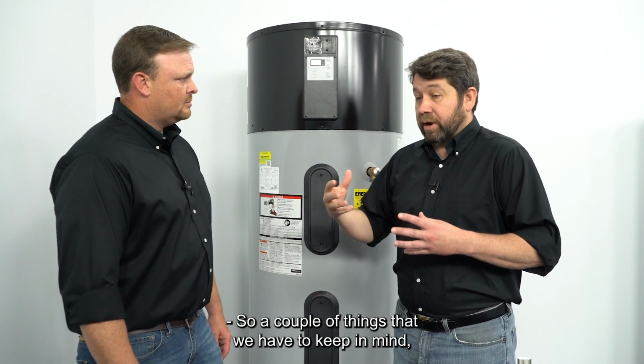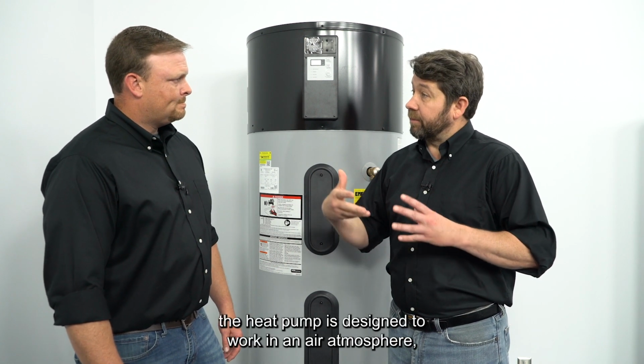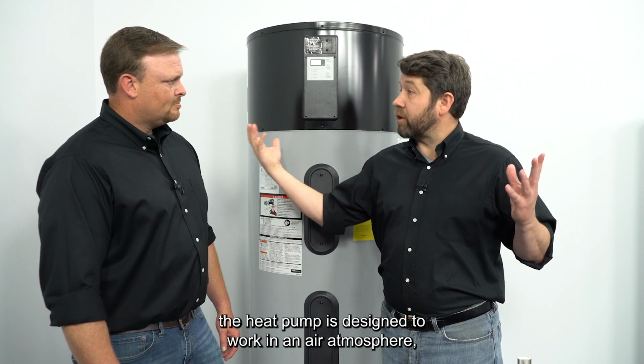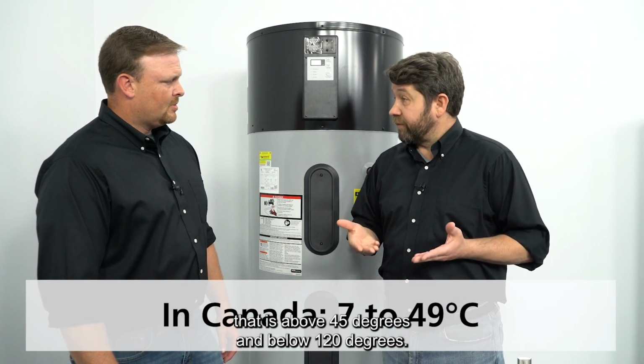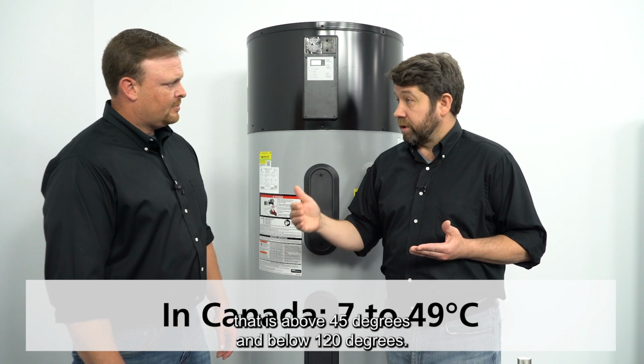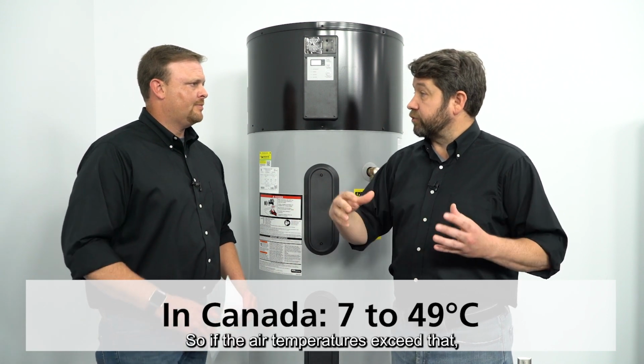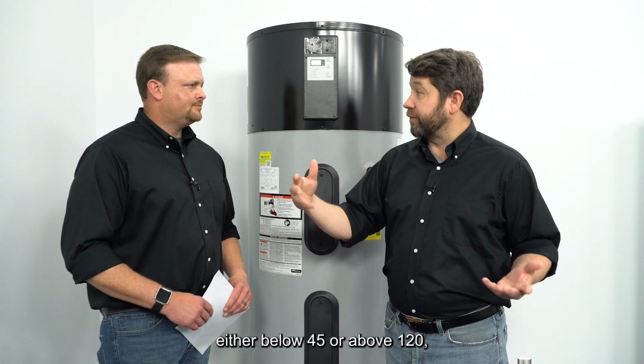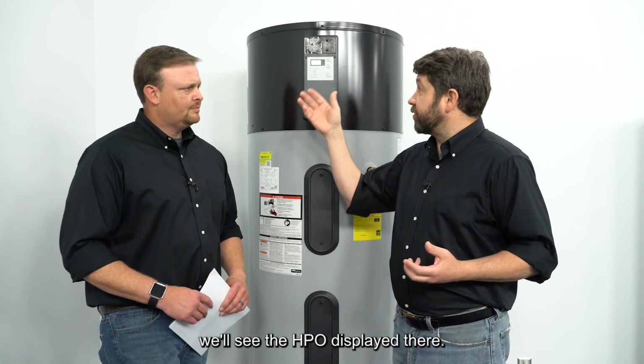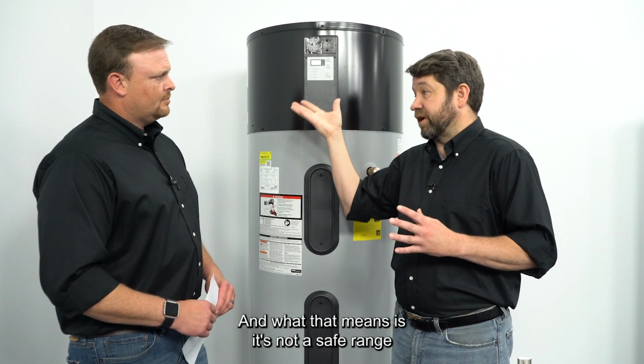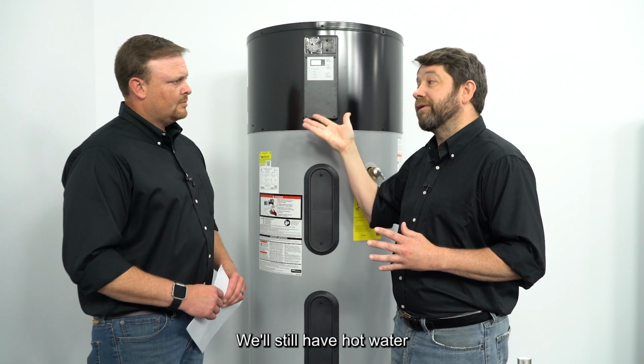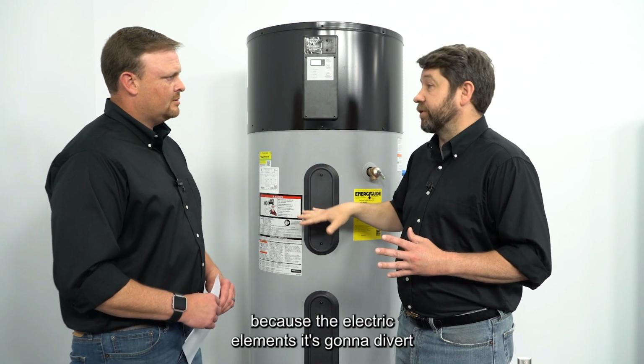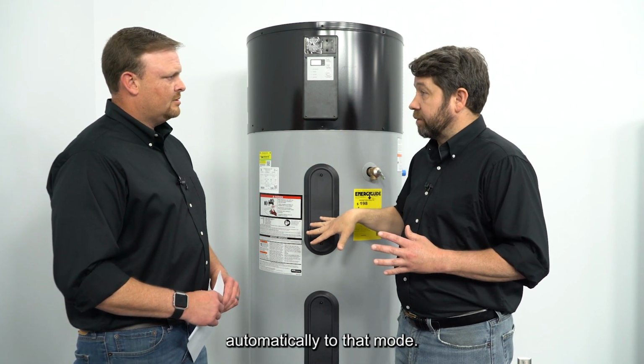So a couple of things that we have to keep in mind. The heat pump is designed to work in an air atmosphere that is above 45 degrees and below 120 degrees. So if the air temperatures exceed that, either below 45 or above 120, we'll see the HPO displayed there. And what that means is it's not a safe range for the heat pump to work. We'll still have hot water because it's going to divert automatically to the electric elements.